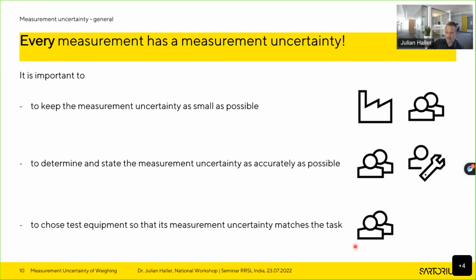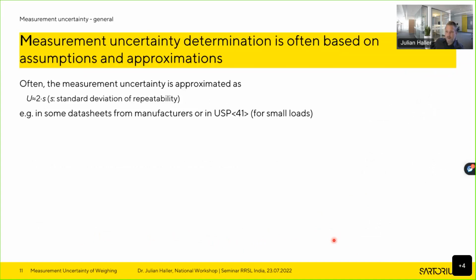So a very brief, simple example: if you want to measure something in the microgram range, you should not buy a weighing instrument with a scale interval of a milligram. That is, I think, clear to everybody. But nevertheless, it is the user's task to make considerations before buying test equipment that the measurement uncertainty matches the respective task and the required accuracies. Now, measurement uncertainty determination, as mentioned, usually follows the previously mentioned GUM as a document, but there's not the one correct determination of a measurement uncertainty because it is usually based on assumptions and approximations. So if you let two different experts or persons do a measurement uncertainty determination for your instrument, you might get two different results. So there's not the one single truth actually.